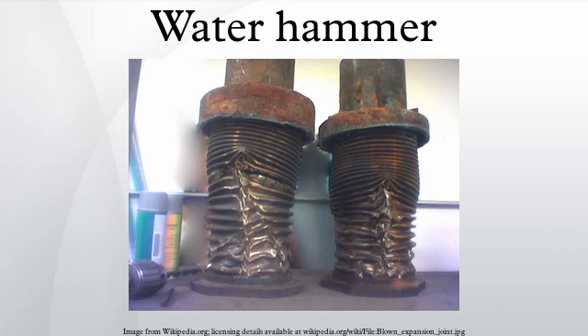Air traps or standpipes are sometimes added as dampers to water systems to absorb the potentially damaging forces caused by the moving water. In hydroelectric generating stations, the water traveling along the tunnel or pipeline may be prevented from entering a turbine by closing a valve. However, if, for example, there is 14 km of tunnel of 7.7 m diameter, full of water traveling at 3.75 m/s, that represents approximately 8,000 megajoules of kinetic energy that must be arrested.